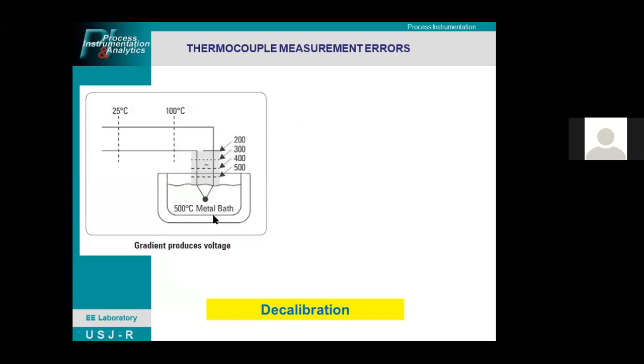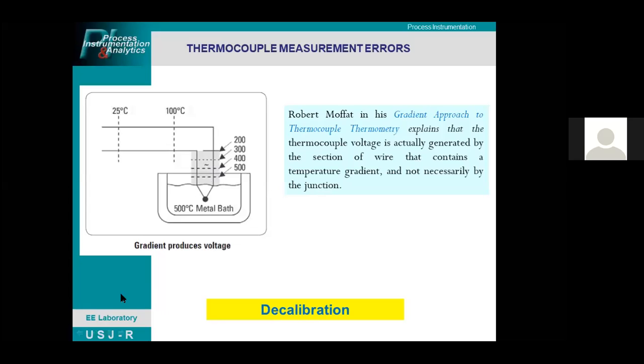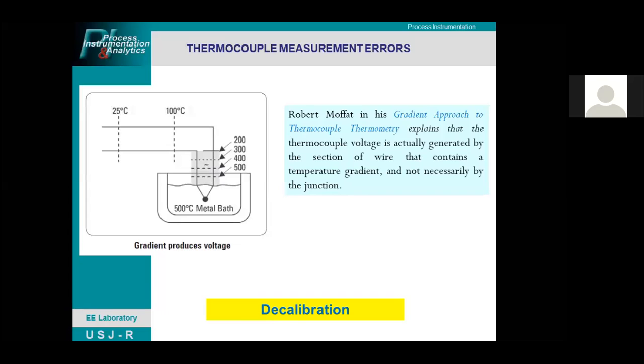Okay, so we have this metal in the bath at 500 degrees centigrade. So this portion could be 200, 300, 400, 500 degrees centigrade. So according to Robert Moffat, in his gradient approach to thermocouple thermometry, the thermocouple voltage is actually generated by the section of wire that contains a temperature gradient and not necessarily by the junction. Okay, so temperature gradients, not the junction itself.